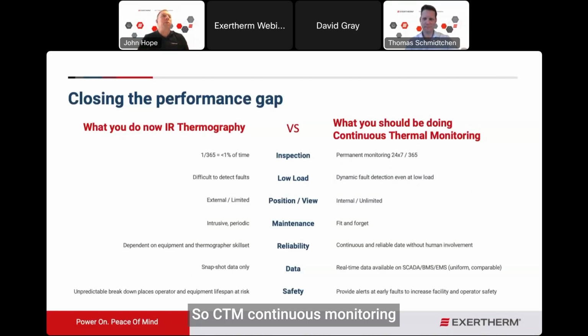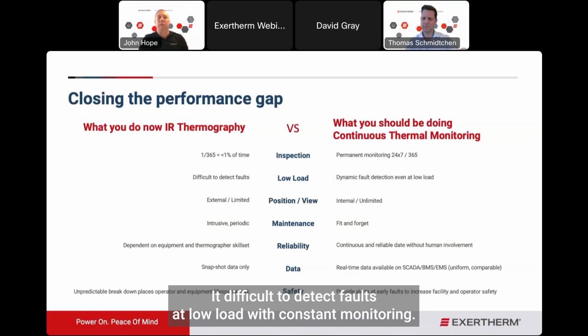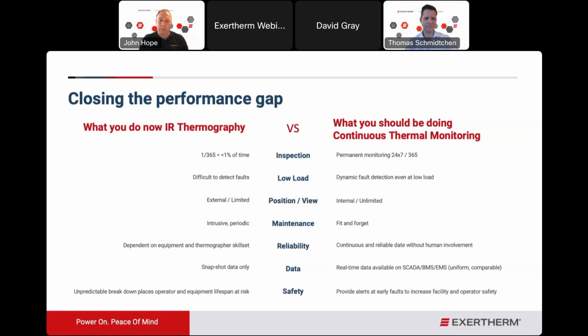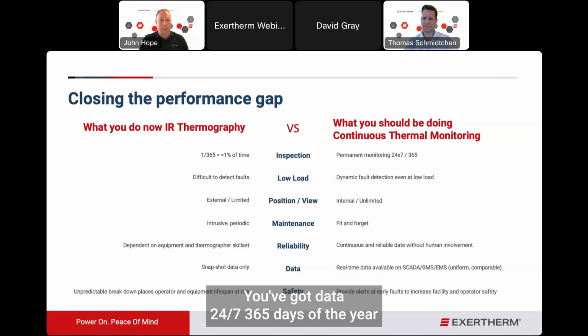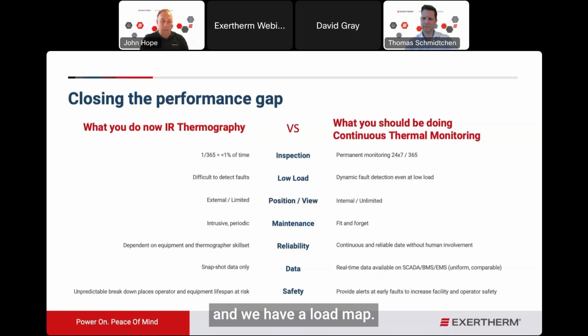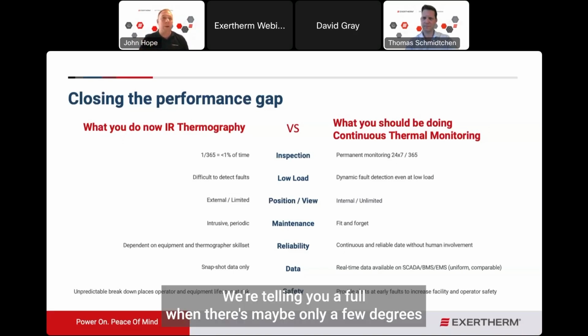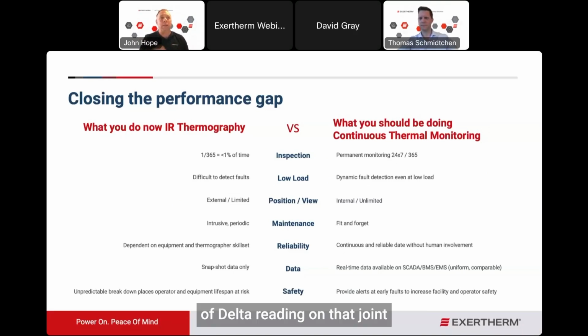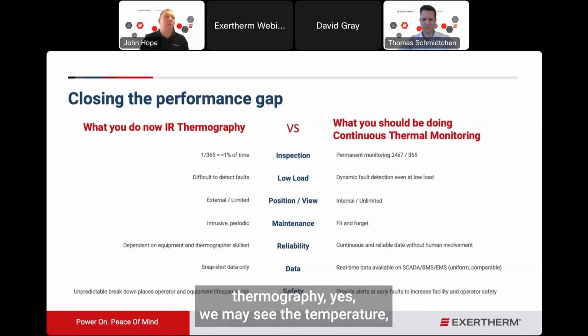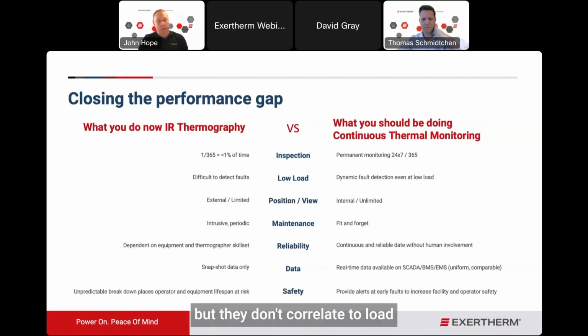So CTM, continuous monitoring, it's closing the performance gap. We know thermography is less than 1% of that uptime. It's difficult to detect faults at low load. With constant monitoring, you've got data 24/7, 365 days of the year. And we have a load map, a piece of patented software, which by using the thermal data and load data, we can actually predict faults at a very, very early stage. We're telling you a fault when there's maybe only a few degrees of delta reading on that joint. A thermographer, yes, they may see the temperature, but they don't correlate to load and can't give you that indication.